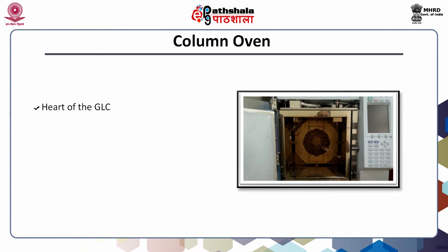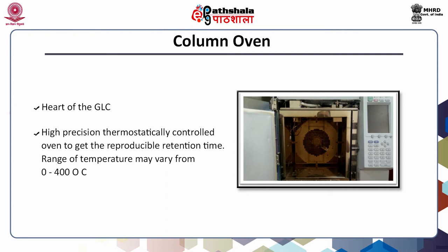Another very important component of GLC — sometimes called the heart of GLC — is the column oven. The efficiency of resolving the components in GLC analysis is temperature dependent. A high-precision thermostatically controlled oven is required for reproducible retention time and results. The temperature range is from 0 to 400 degree Celsius, maintaining a temperature from plus 10 ambient up to 400°C.